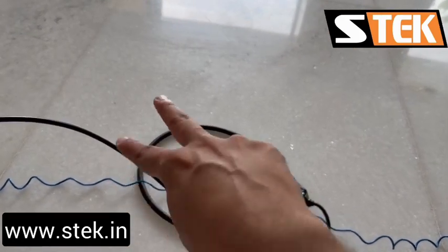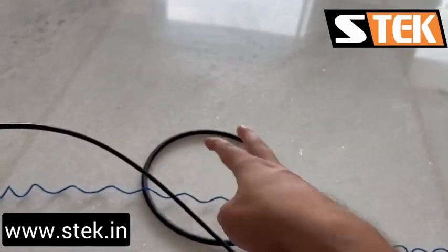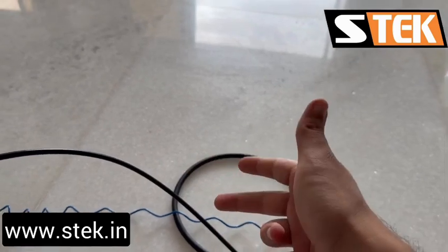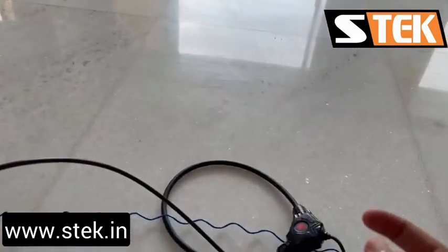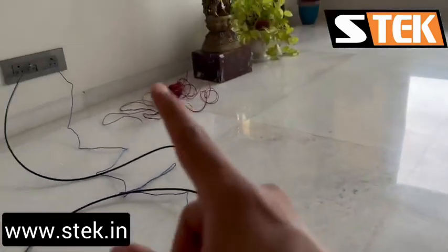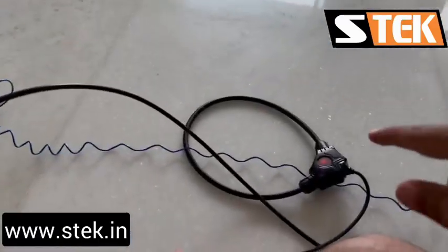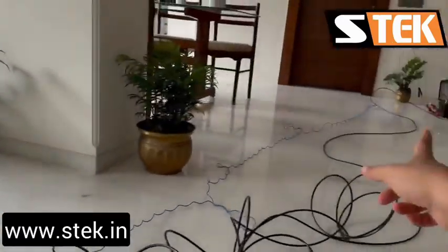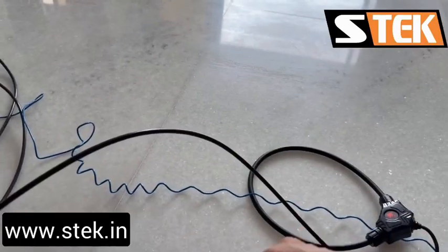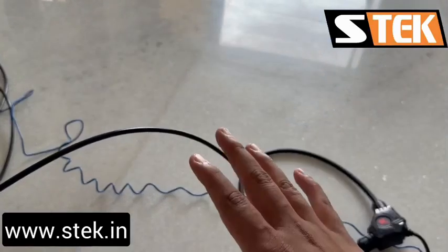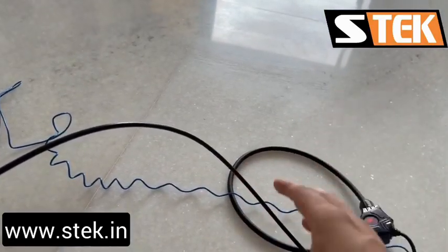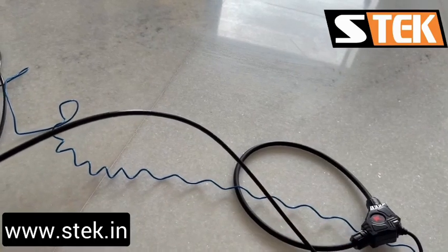This helps you avoid having to cut, or even in a single core cable like the blue one, you don't need to loop around and check for continuity. You just need to make sure both sides are earthed, then you can do a calibration on the end you're transmitting from, and test on an unknown section. Remember, calibration always needs to be done on an area where you know for sure which cable is yours.